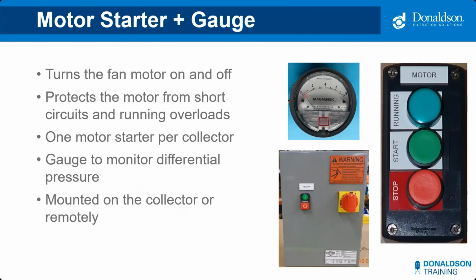Similar to a cyclone, a mist collector that utilizes draining will most likely just have a motor starter. But you also will need some type of gauge to monitor the differential pressure. This tells the operator the condition of the filters. The motor starter can either be mounted on the collector, like we saw in the picture earlier, or it could be mounted somewhere else in the facility and started remotely. Remote starters are often used when the collector is located in a place that is impractical to have a control panel. Think of a collector located outside, especially in the weather we've all been experiencing recently. You would want the controls to be inside the facility and temperature controlled.